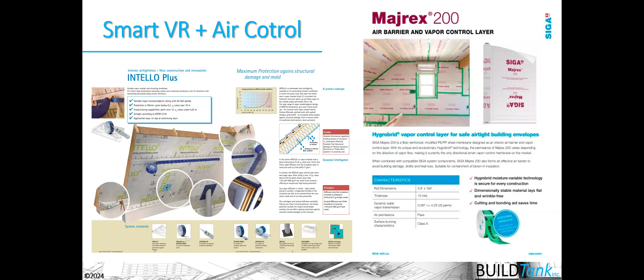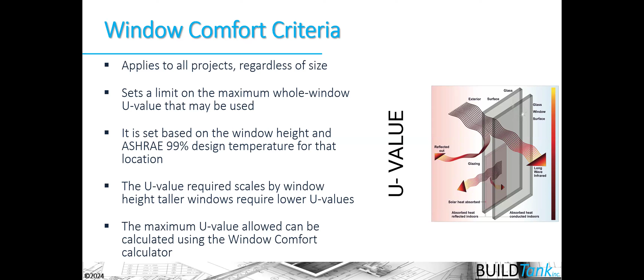Let's move on to window comfort criteria. Windows are another place where you're going to potentially get condensation if the R value or U value of that window assembly is not good enough to create an adequate surface temperature on that window. In the example that I gave, that surface temperature had to be in excess of 40 degrees to ensure that air at 35% relative humidity and 70 degrees doesn't create condensation on that glass. So the PHIUS system has some window comfort criteria that dictate the U value of the window that we have to achieve. It's from a comfort perspective, but it's also from a condensation perspective.